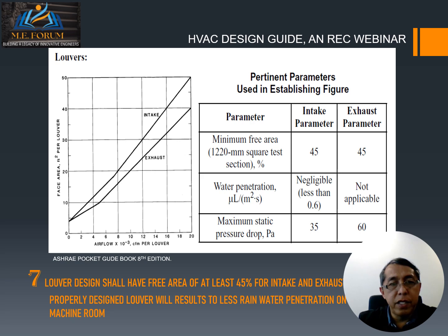Number 7, louver design shall have a free area of at least 45% for intake and exhaust. Properly designed louver will result in less rain water penetration in the machine room.